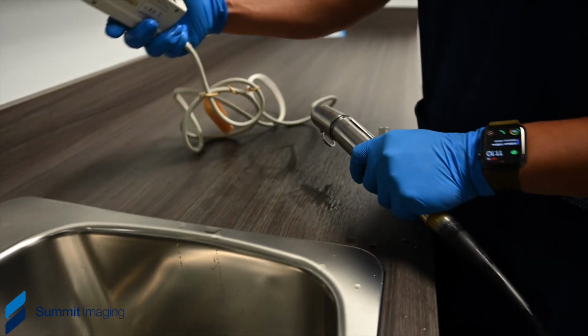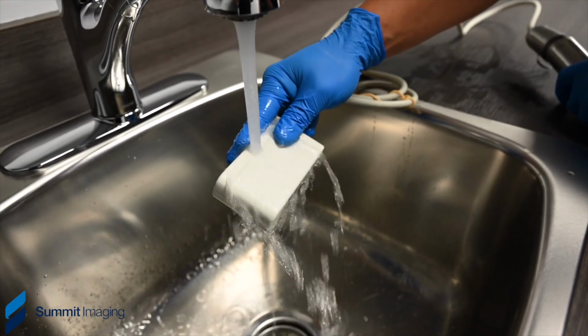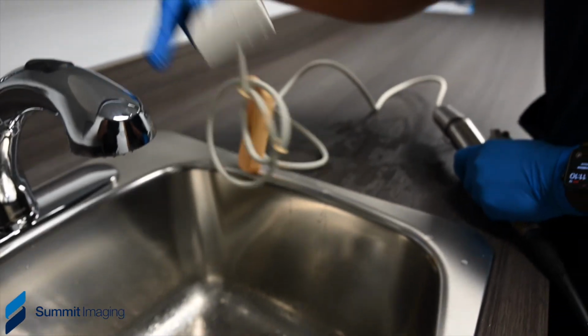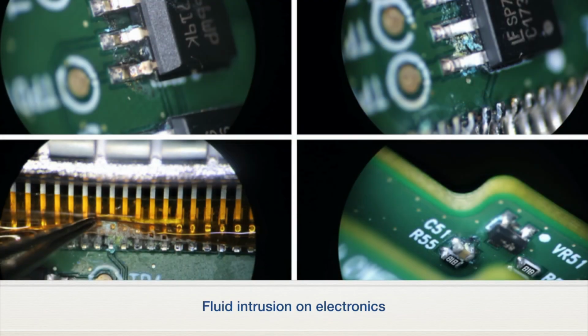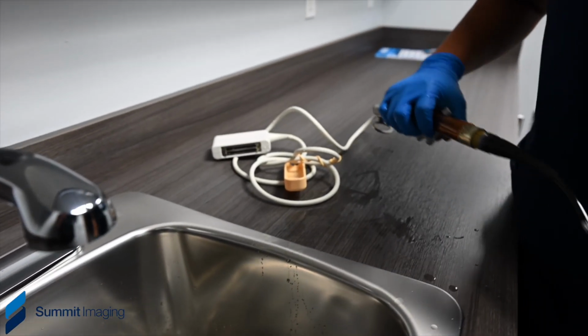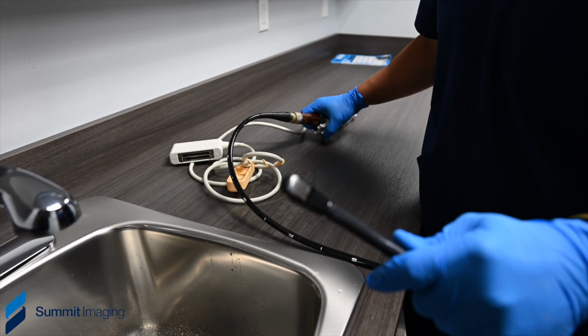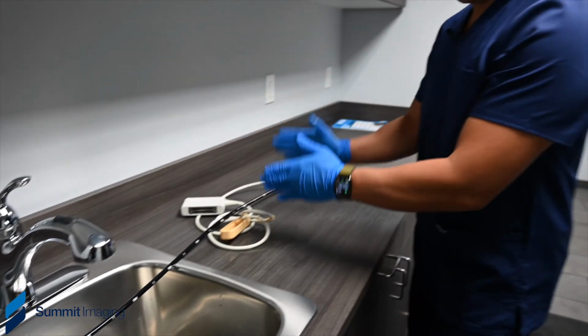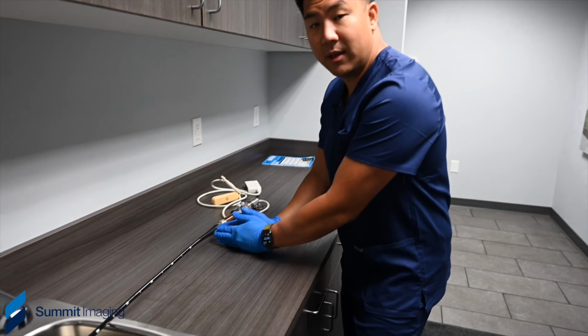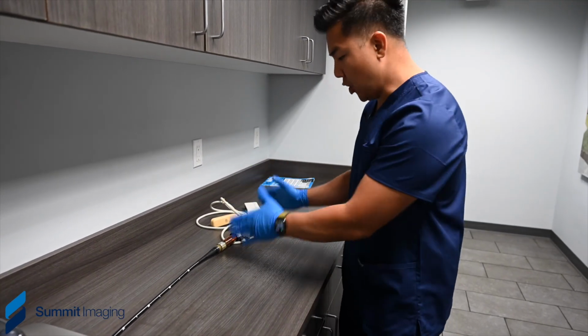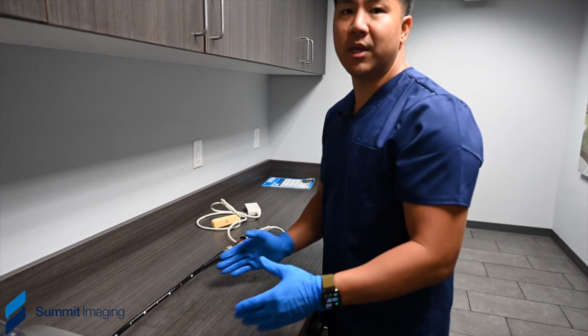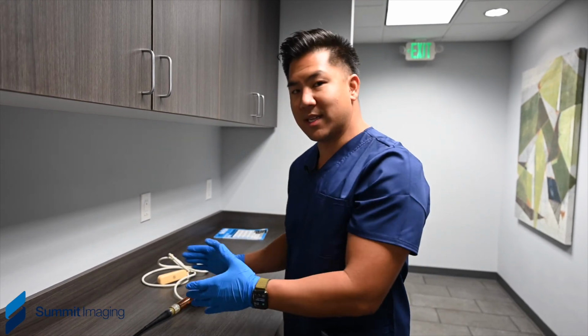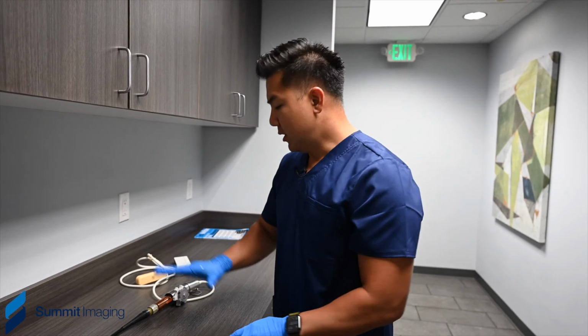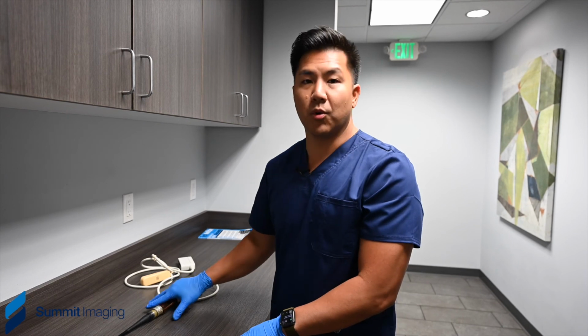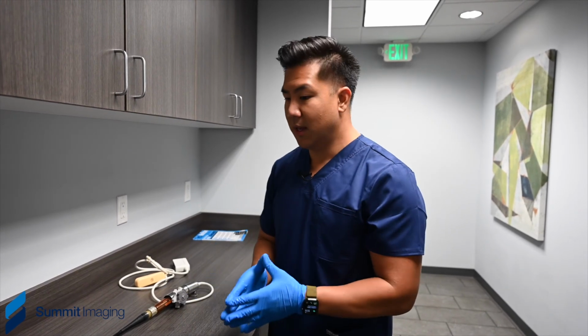We've even seen so much so where technicians will actually wash the connector where all the high voltage electronics are stored, causing massive shorting inside this connector, and therefore shorting here. The circuits run all the way up the probe and can short your crystal at the same time. So a lot of slippery surfaces here. Do not drench the fluid behind the insertion tube. You can wipe this down, but don't soak it. We've also seen the handle and the connector being soaked in the baths that actually decontaminate the probes post this rinsing process. Or it slides into the decontamination receptacle. Don't want these. Keep these dry as much as you can. Do not immerse these in any fluids, or you will get a lot of failures and take the equipment out of commission.